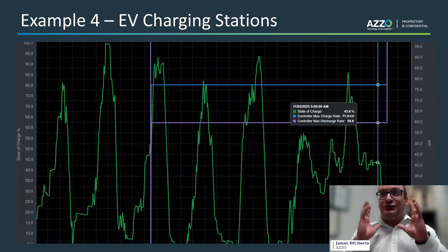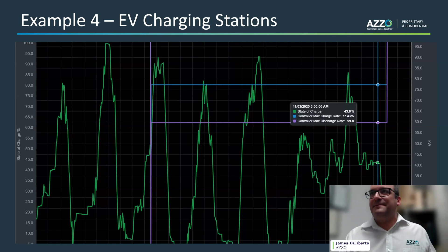I'll go through this next one quickly. This is an example with large-scale fast chargers in a small location with a small connection. Rather than paying $500,000 to install a larger transformer, why not install some PV and battery storage, controlled in a way that prioritizes load control and then takes secondary benefits like spot market participation and frequency ancillary services when it's not doing that primary job? The speed to get those chargers in and operational was extensive. Also, while the battery isn't being used for peak management, it can be used for things like arbitrage. Controlling those chargers, all of these things working together, avoided the transformer upgrade.